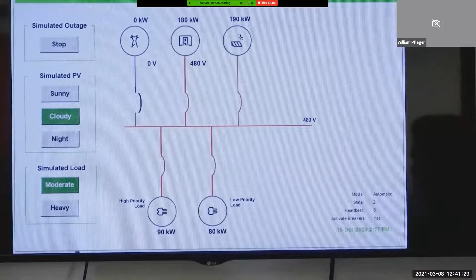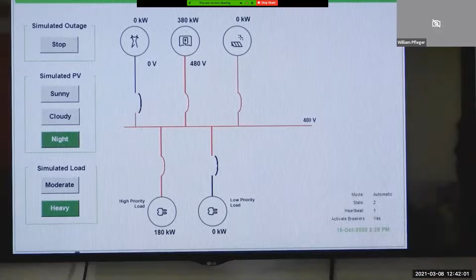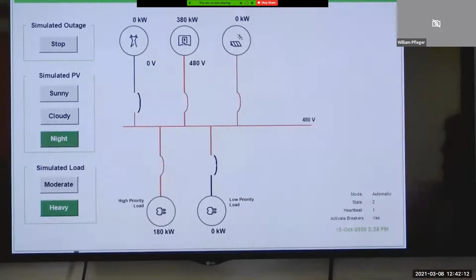So let's take a listen and see what happens if the load were to step up to heavy. Bet you heard that. So that is the lower priority load breaker opening, and that allows the rest of the system to continue to be powered. So the high priority load stays on, that data center that you don't see attached to the ECC, but that data center is still being powered. And so that 200 kilowatts of data center and 180 kilowatts here on the high priority load is why the generator is at 380, but it can't take more than that.